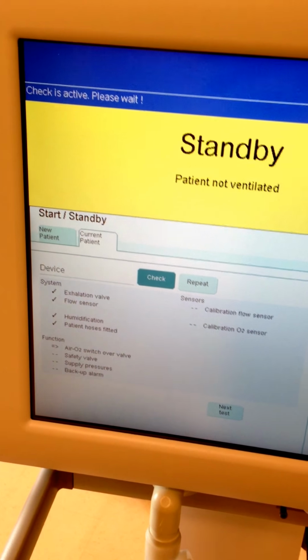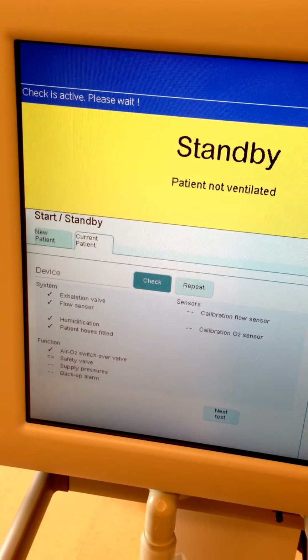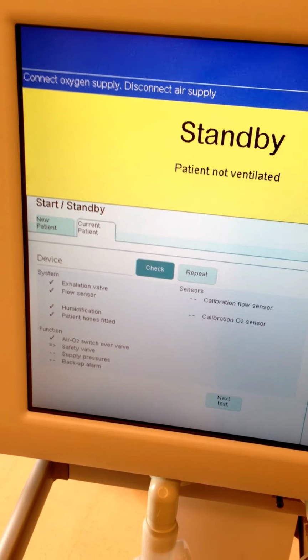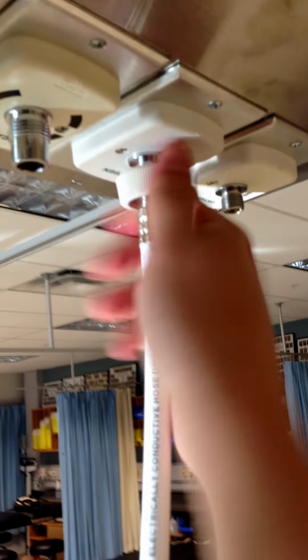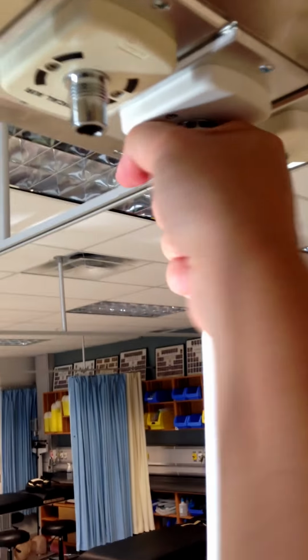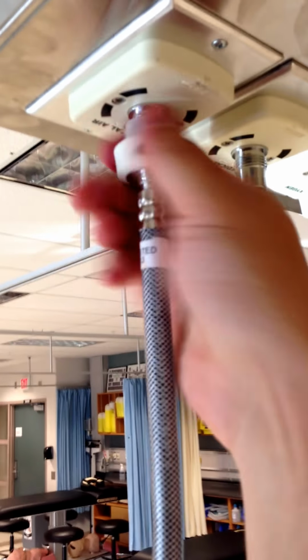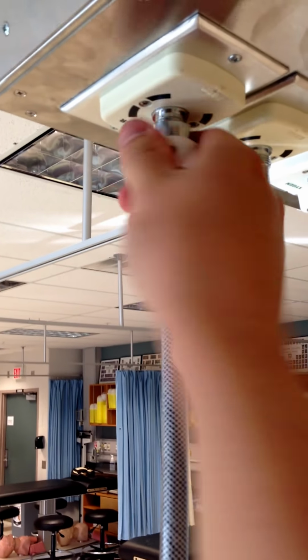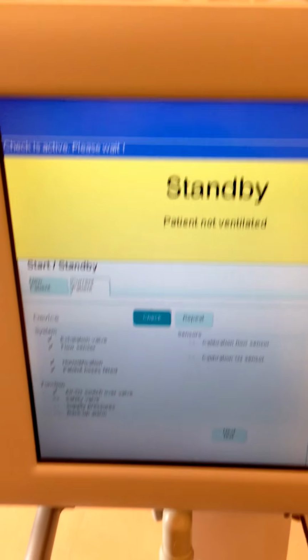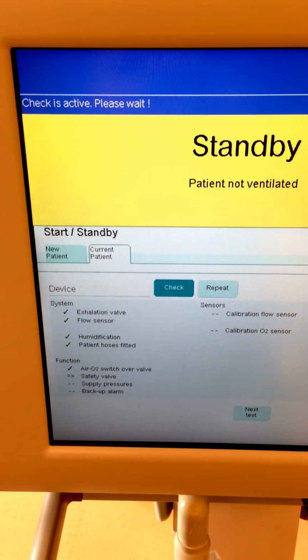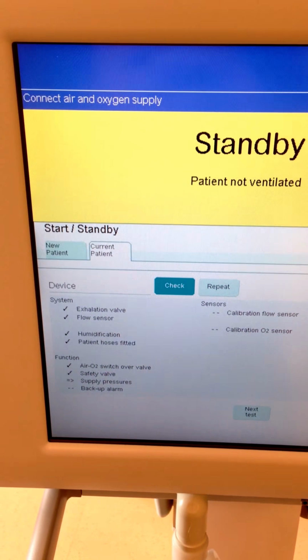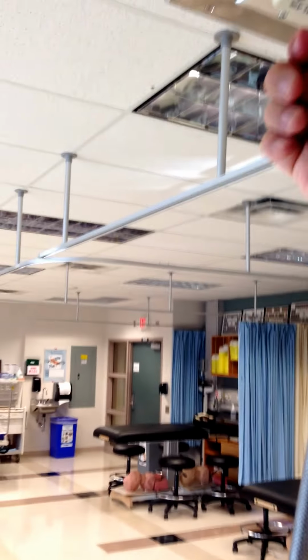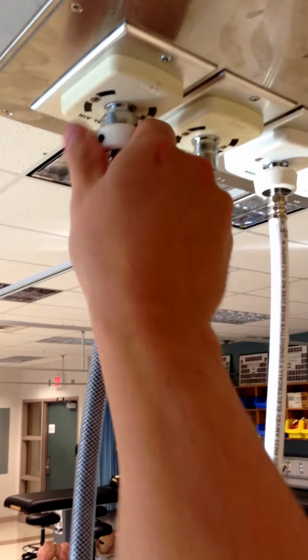It's doing its thing here. Connect oxygen supply and disconnect air. Okay, so this is checking that switchover, the air and O2 switchover. Make sure the internal blenders are working and that there's no leak in the internal high pressure system. So I've disconnected the air. Now connect both air and oxygen supply. Okay, I believe that's the last of the manual labor for this check.